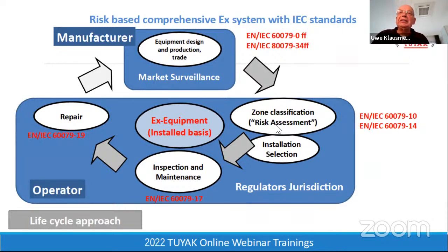So this risk assessment leads to a zone classification. This zone classification makes three classes of risks. A very, very high risk is to be found in a tank. A slightly lower risk you find around the tank. And a lower risk you can find a little bit far away from this tank. It means you have zone 0, zone 1, and zone 2 to classify before you start to construct such a facility. So everything starts with this zone classification according to 79-10.